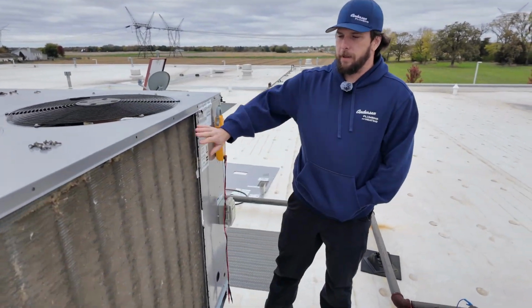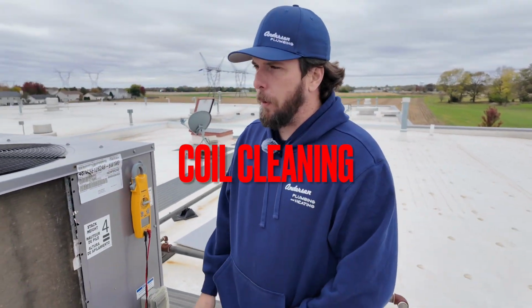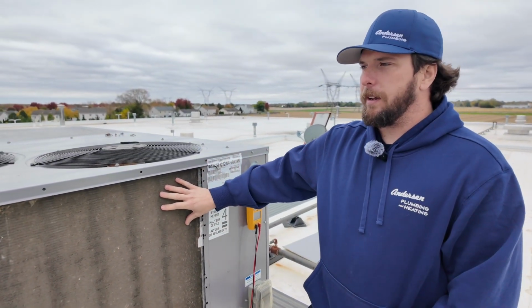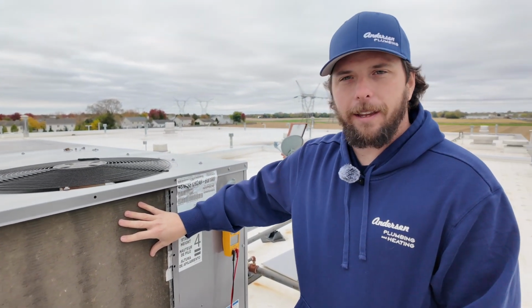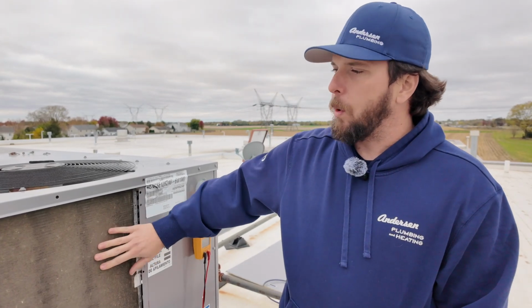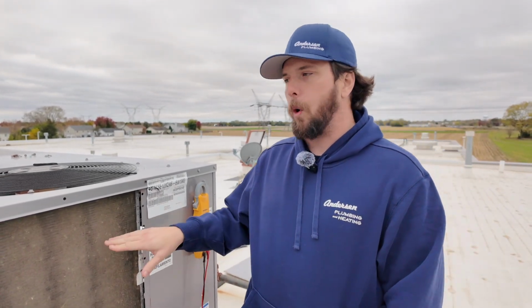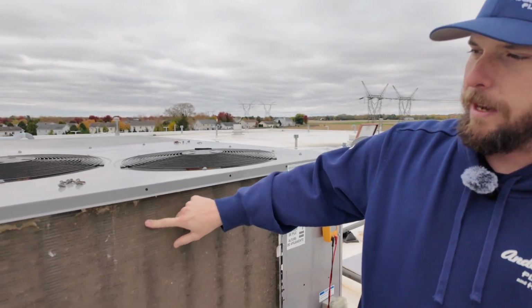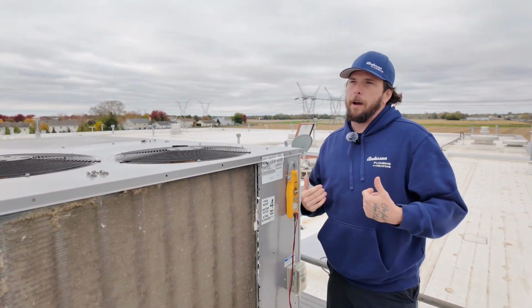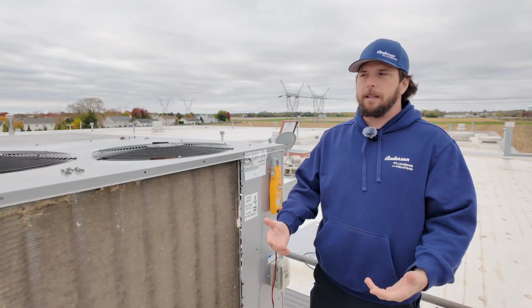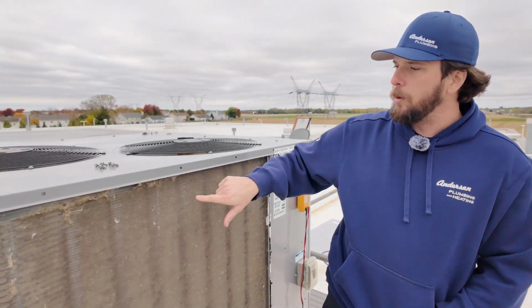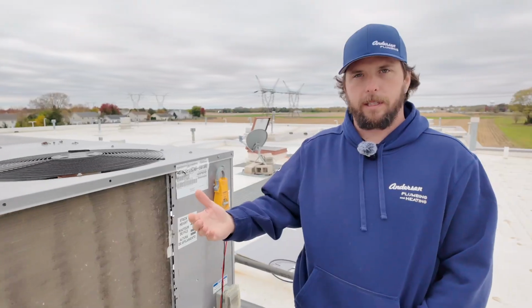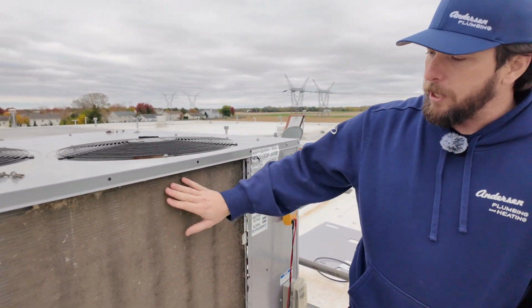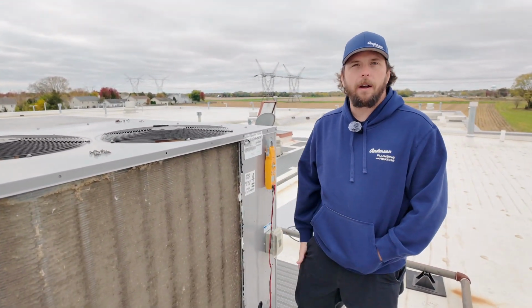So I want to talk about the debris that's on the outside of these coils a little bit more. Them being dirty, obviously, aesthetically, that's not our goal here. Although they do look pretty when we're done, that's not the main focus. All this buildup on the outside of this coil restricts the airflow going through the coil. So all these little slots in here are the way that this thing dissipates the heat. So these coils get hot, the air goes through the coils, and that's how it loses the heat. When you have these restrictions, obviously your airflow is not what it's supposed to be.